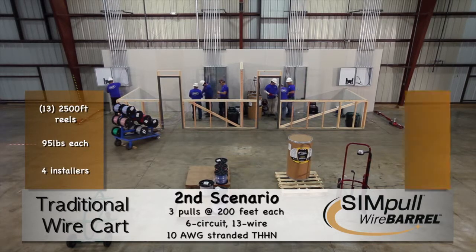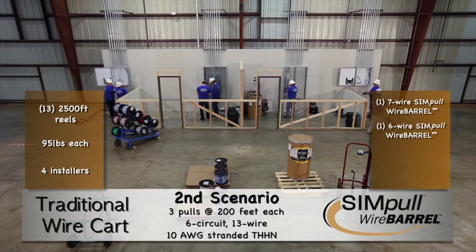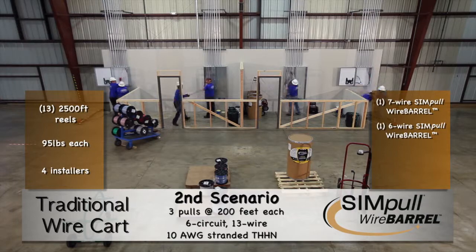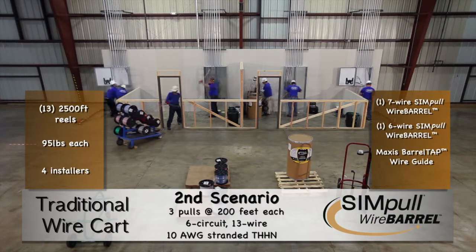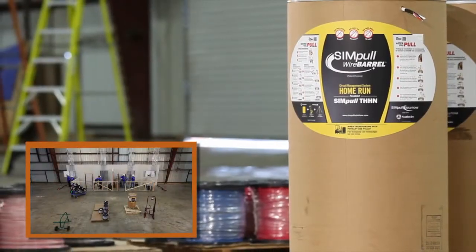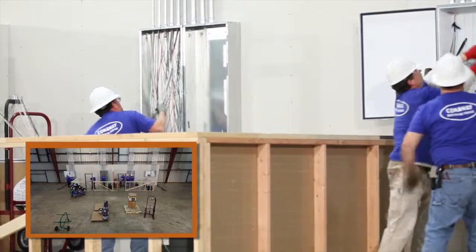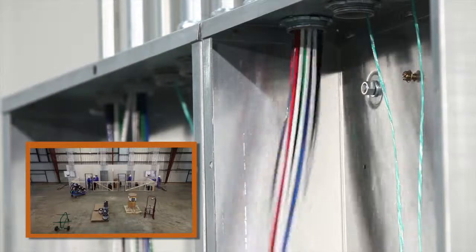On the right, this home run pull is easily accomplished by adding a six-conductor wire barrel package along with the existing seven-conductor barrel package, resulting in a two-barrel combination. In this instance, a Maxxis barrel tap wire guide is utilized with the additional barrel package. Three installers are used on the wire barrel side. During more extensive pulls, using the SIMpull WireBARREL system provides a fluid, consistent way to ensure all conductors are even and easy to group together as they are fed into the conduit.